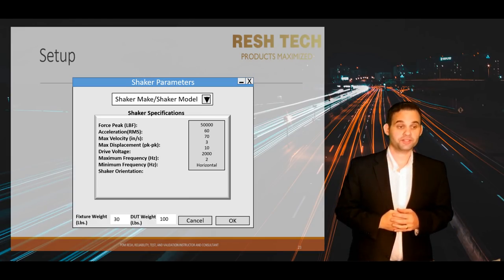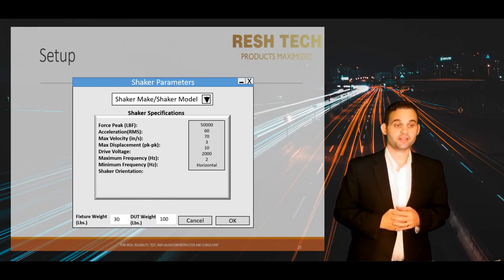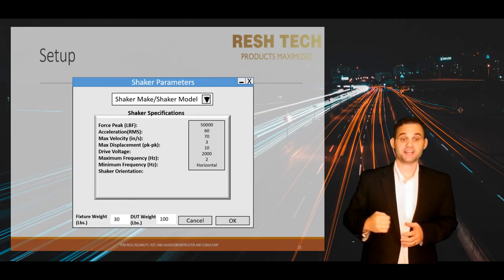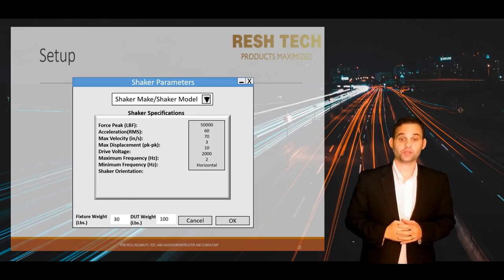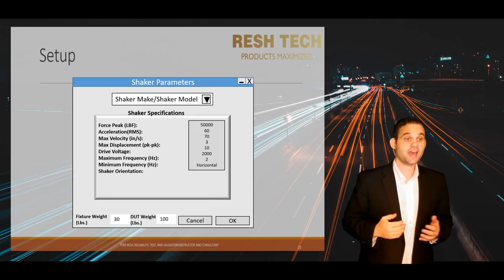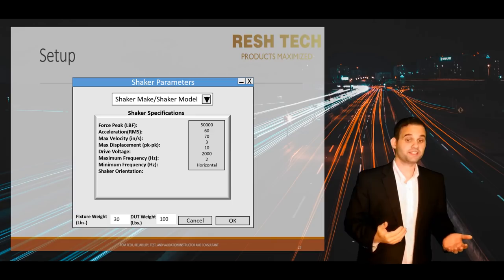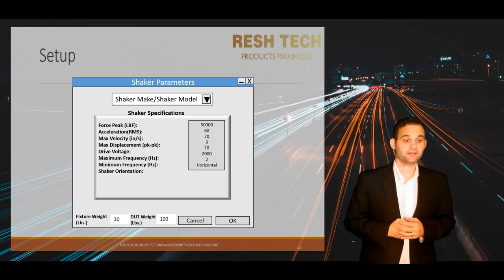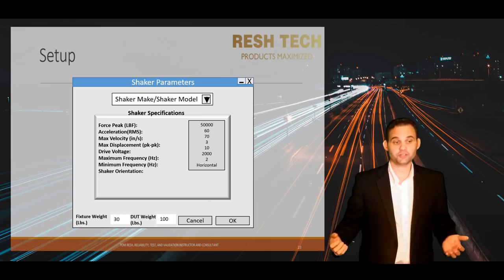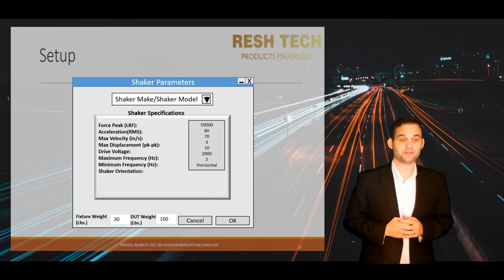If your shaker is a preset in your vibration controller, the only items you will need to update are your test fixture weight and your test unit's weight. Sometimes there will only be a field for the test unit weight — in that case, add your fixture and test unit weights together and enter that combined value in the test unit weight field.